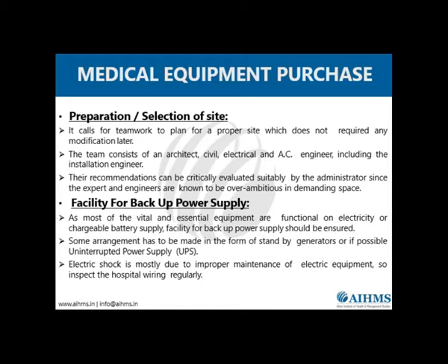Similarly, you should also take into consideration the power supply, because you should know what the power backup is, whether you are going to use a UPS or a whole set of generators, or the other set of equipment required for uninterrupted power supply.